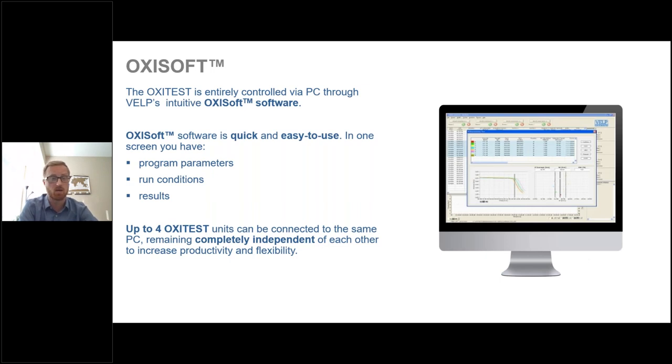The OxiTest software is enabled through a PC and is quick and easy to use. In one screen, you can manage all your program parameters, run conditions, view results, and export them as needed. You can connect up to four OxiTest units to the same PC, and they remain completely independent of each other to increase productivity and flexibility — for a total of eight samples.